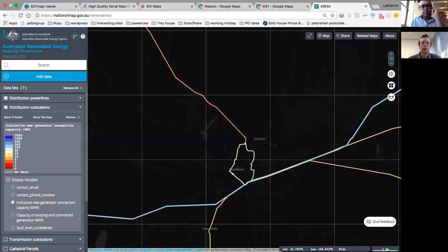For anyone dealing up to about a megawatt in size, avoid anything over 33 kilovolts — that's the lowest of the distribution feeders. If you're dealing at a 10 or 100 kilowatt scale, look for something relatively close to the transformer down the street, which you can see on Google Maps Street View. Follow your power lines, find your transformer, and make sure you're not too far away, since distance can add to the constraints you face.